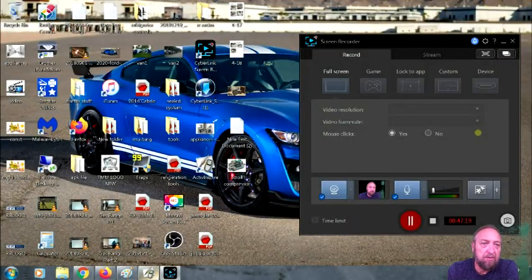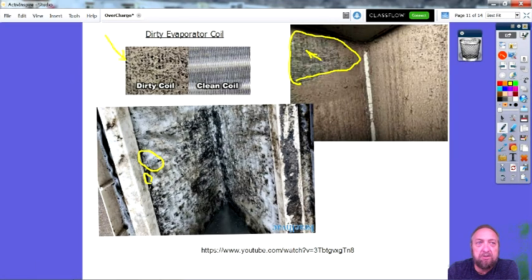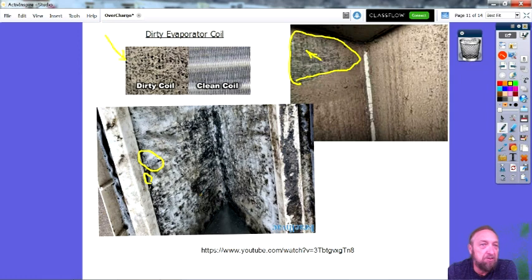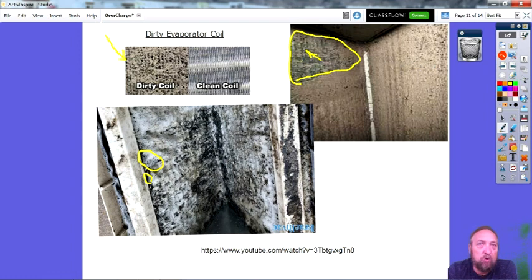You can actually see a little bit of the evaporator coil sticking through the foam. Coil cleaner used on an air conditioning unit gets inside, foams up, and pulls the dirt out. Some people charge between $200 and $400 to do a coil clean. It takes about 45 minutes to pull the coil out, spray cleaner on it, hose it down, put it back in, charge it back up. When dirty, dirt gets in between the coils — the coils are wet with humidity and the dirt sticks to them.